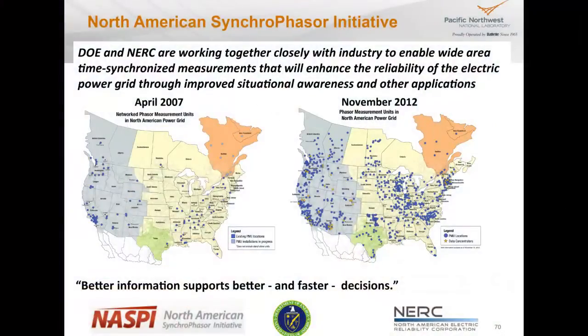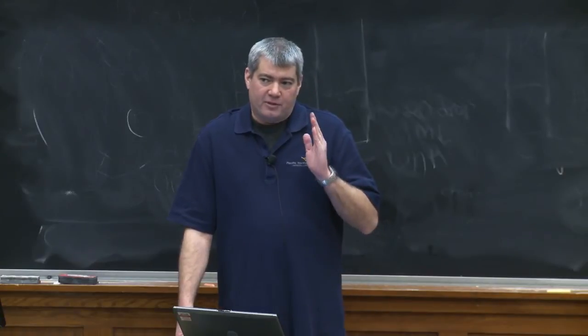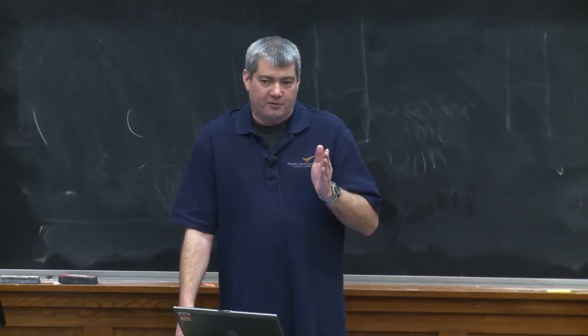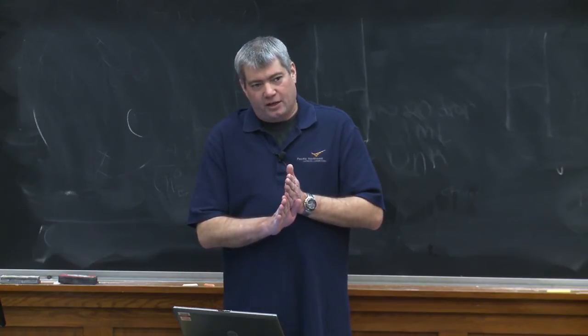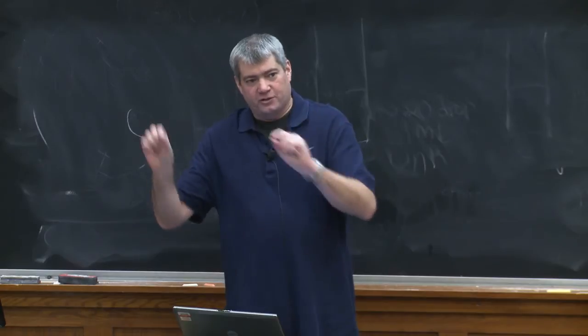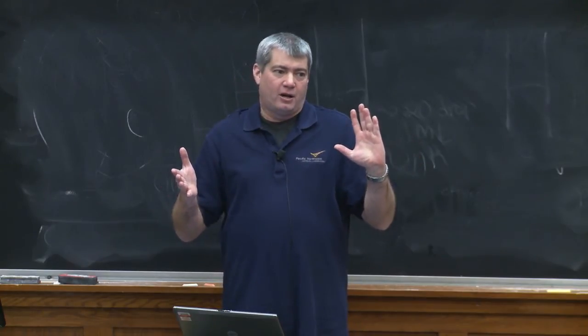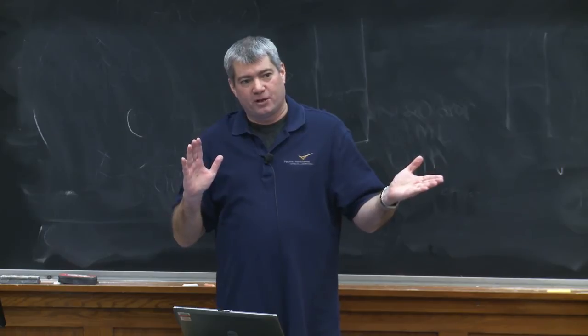So I also can't resist throwing in a couple slides on some of my pet projects. One is the North American Synchrophasor Initiative, a joint initiative between NERC and DOE to deploy, implement, and utilize data from phasor measurement units. A phasor measurement unit has a common time reference—we use GPS for that—and it calculates the relative crest of voltages at different parts of the grid, so we can measure relative phase angles between different parts of the network.